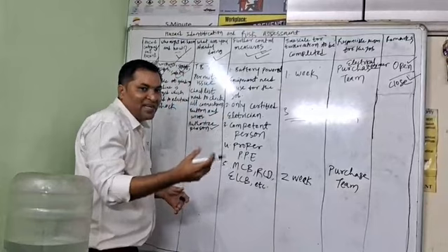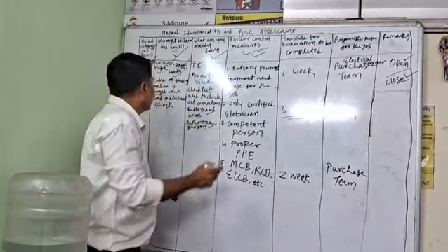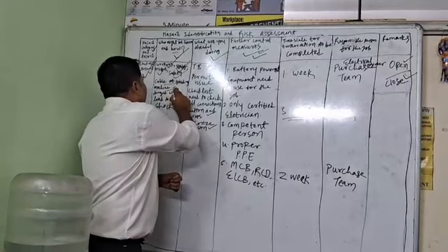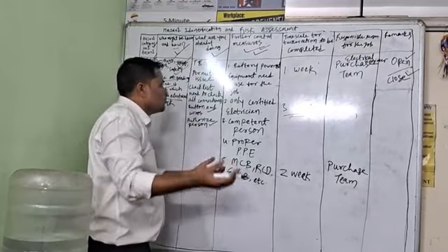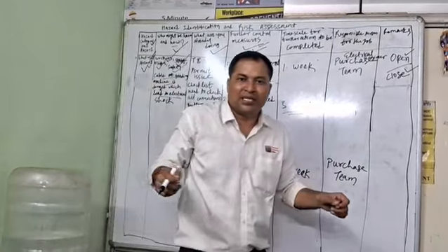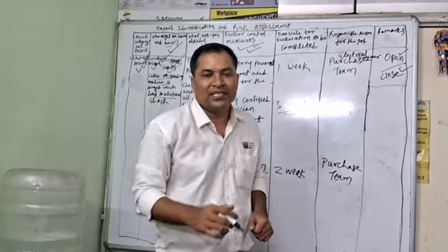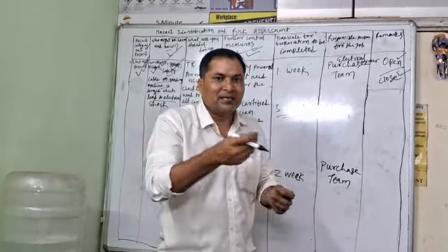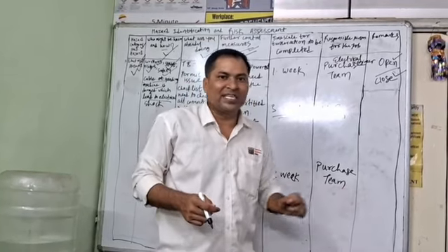How will they come in contact with electrical equipment? Electrical shock due to a damaged cable of a grinding machine, which may lead to electrical shock if the wire is damaged and people are roaming on top of the same wire, so they might get shocked due to the damaged electrical wiring. So you need to check that.